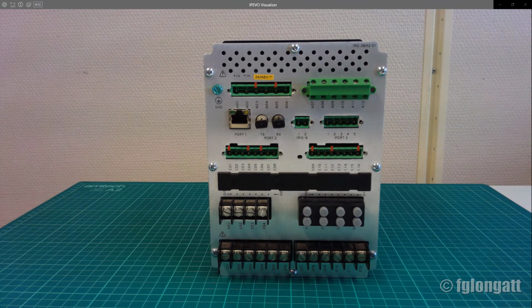But regarding current transformer, the current transformer inputs are located here, and we are using 1 amp phase for the AC current input. Regarding the voltage, the secondary of the voltage transformer, we are assuming that we will use here almost until 300 volts AC. However, those terminals are designed for much more. They are tested for 600 volts AC over 10 seconds.